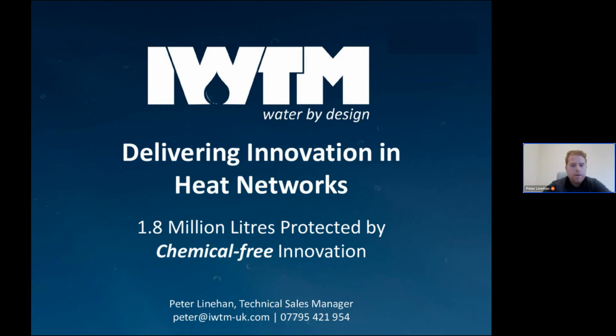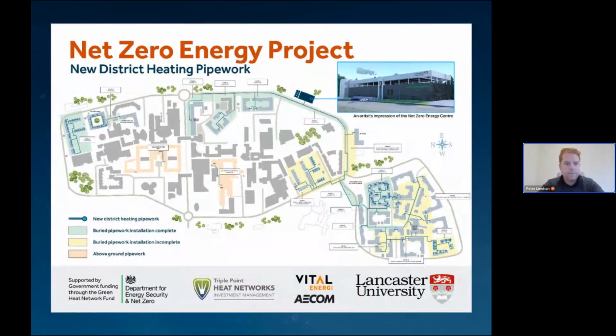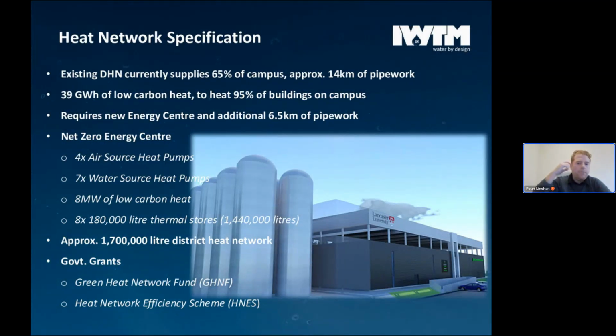Today we're going to be talking about a very large district heating system protected by chemical-free water treatment. Some of you may know it as LUNZIP—Lancaster Uni Net Zero project. It's an existing district heating system supplying heat to around 65% of the university campus, about 14 kilometers of underground pipework, and they want to expand it so it provides heat to 95% of the campus, which means an additional 6.5 kilometers of pipework.